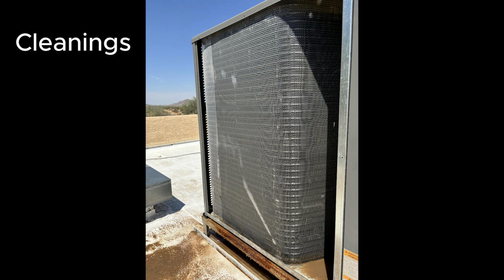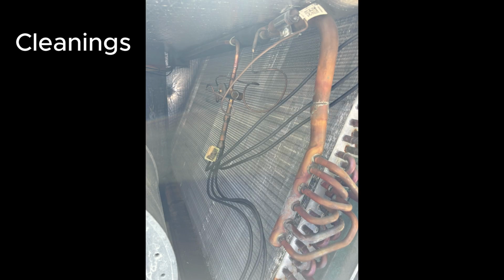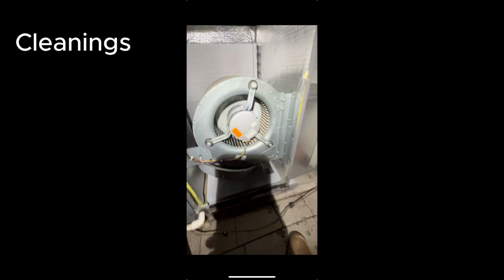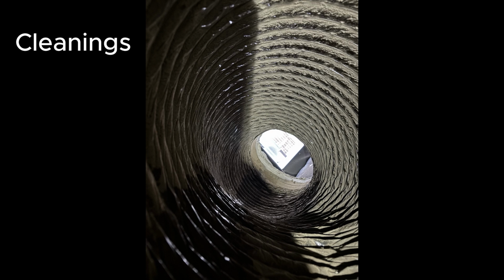This is a picture of a condenser coil, and what we're going to talk about here for just a second is cleaning. So what a lot of technicians offer during maintenances are cleanings, and they're worthwhile. The big thing here is cleaning coils, cleaning the blower motor. That improves the efficiency and the longevity of the system, and they are worthwhile. It's nothing catastrophic, but it's preventative maintenance, and cleanings are definitely good for improving the efficiency of the system.